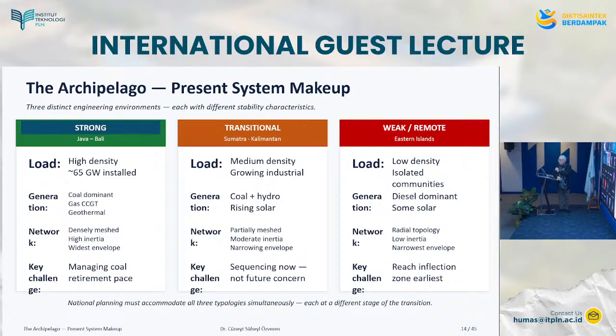Now, small isolated systems face a stability challenge that large interconnected systems don't, because large interconnected systems can transfer power from generators in other regions. For example, a 500 megawatt generator trip on the Java Bali system, with an H constant of 5 seconds and 25 gigawatt peak, causes a change of power event of about 2%. Well, the same trip on a 1 gigawatt outer island system causes a change of power event of 50%. So the same power loss has a bigger impact on a smaller system than on a bigger system, right?